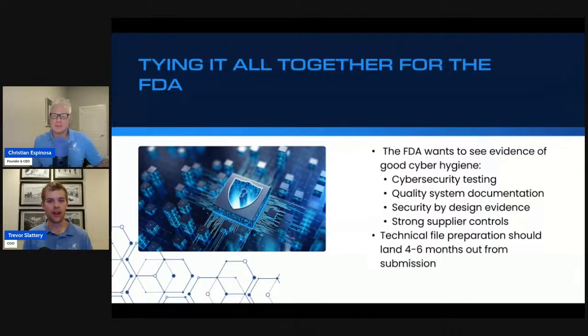Now, why it's important to have about this window instead of preparing it, say, 12 months, 18 months, 24 months out, is that we need to have a level of recency within our cybersecurity testing. That's one very common kickback that we see from the FDA: your cybersecurity testing was not done recently enough. Generally, the rule of thumb is that testing is valid for 12 months. However, in some cases, we have seen 6 months as sort of the rule of thumb to follow. We try to take a little bit more of a risk averse approach to doing this, which is why we recommend 6 months as the maximum you should be out from your submission.